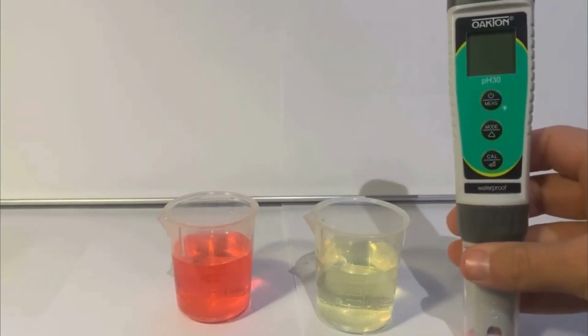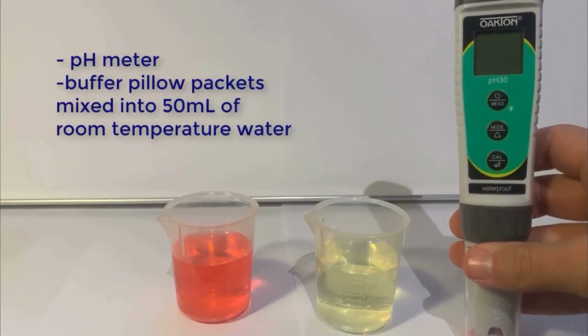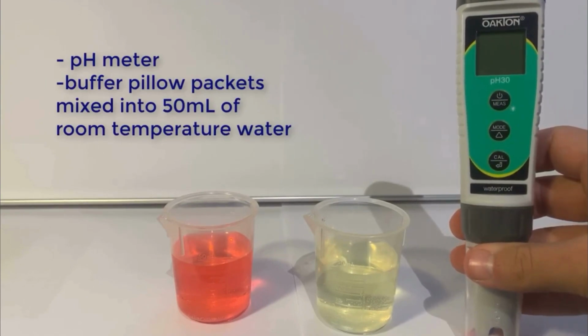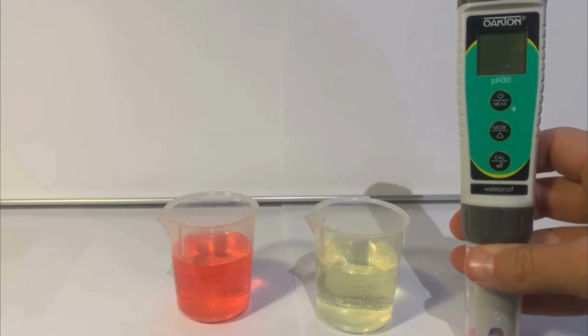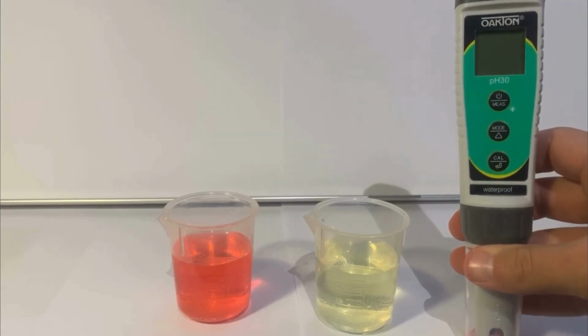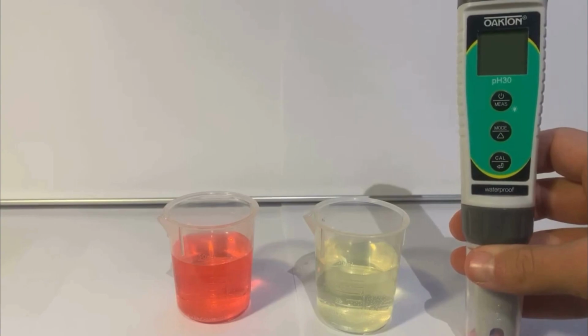You will need your pH meter, your pillow packets that bracket your normal reading mixed into 50 milliliters of room temperature water, and a cup of water or your squeeze bottle to rinse off your probe. If you haven't used your meter in a few months or the bulb appears cloudy or dry, soak your pH meter in Buffer 4 solution for about 30 minutes to rehydrate it before use.